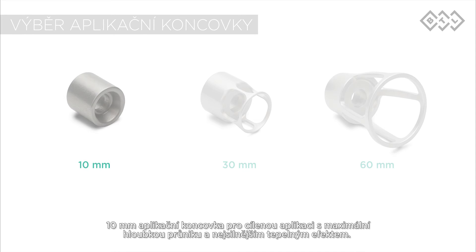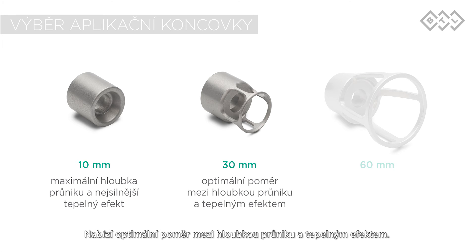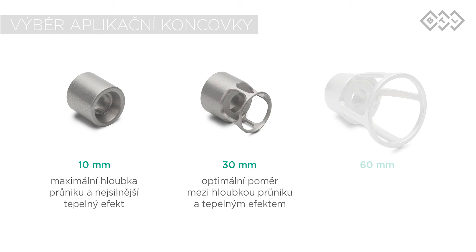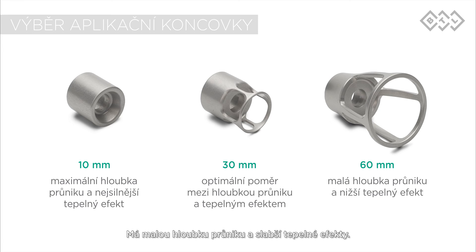There are three spacers available. A 10 mm spacer is for focal application with maximum penetration depth and the strongest thermal effect. A 30 mm spacer will be optimal for most applications, featuring an optimal ratio between penetration depth and thermal effect. A 60 mm spacer is suitable for superficial applications; it has a low penetration depth and a lower thermal effect, and is suitable for the treatment of acute and superficial conditions.